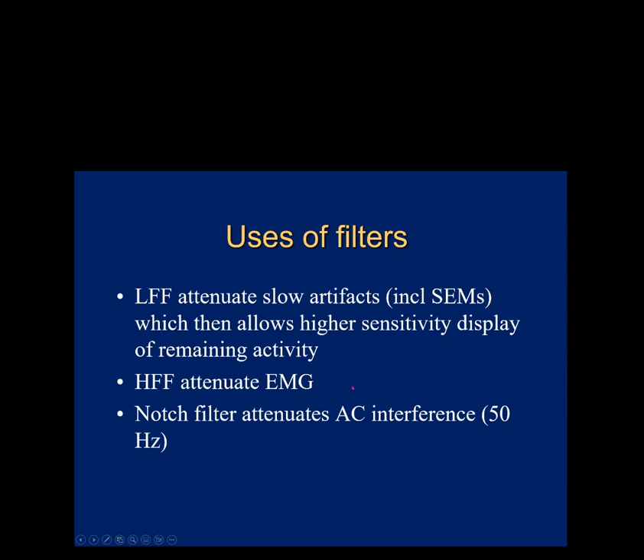The problems they cause is they can conceal poor technique. So it may be that an electrode has fallen off the head, nobody's noticed, and the EEG still looks okay because filters have got rid of those frequencies that would have told you that there was a major problem. I mentioned making EMG look like brain waves. It can also conceal pathological activity. So there might be slowing there, and if you turn up the low frequency filter too much, you won't see it.